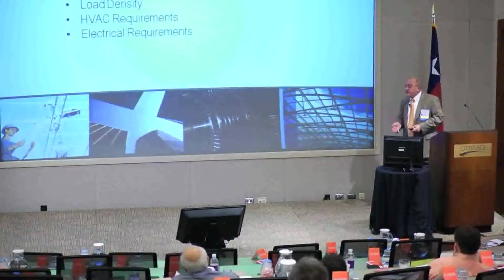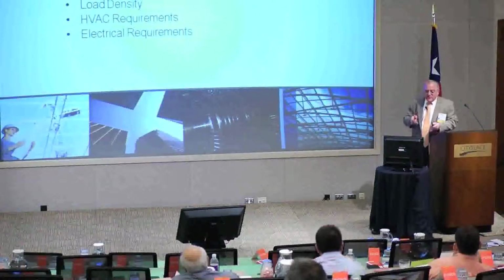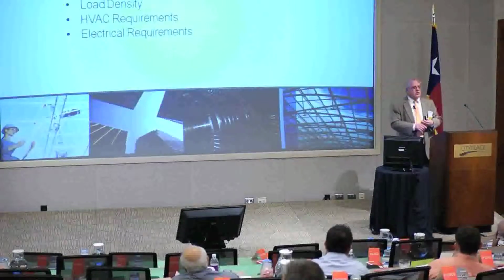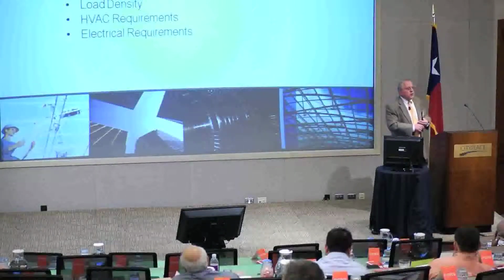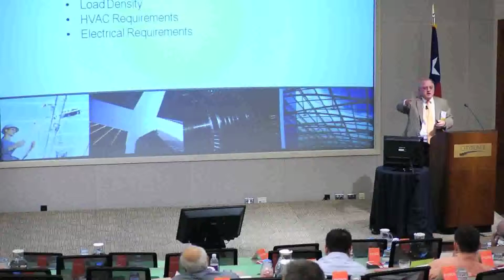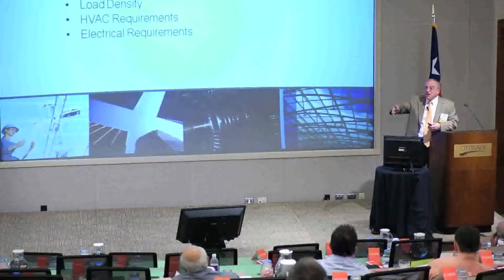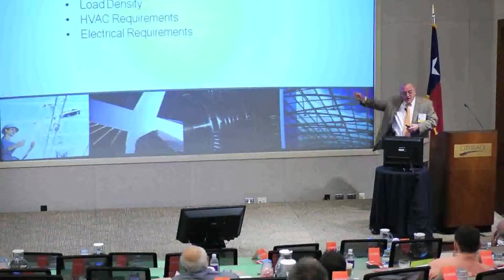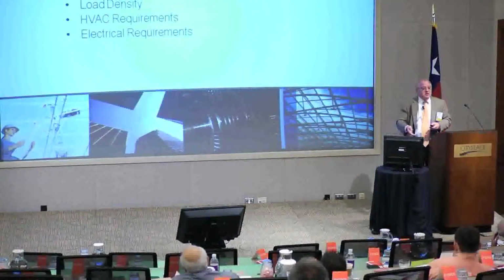Sometimes the MEP spaces may be a larger element than the white space. What is my load density? That's day one. Then when you look into your crystal ball, where will your load be at 3 years, 5 years, 15 years, at the end of life of your first cycle of equipment? What are your HVAC requirements?